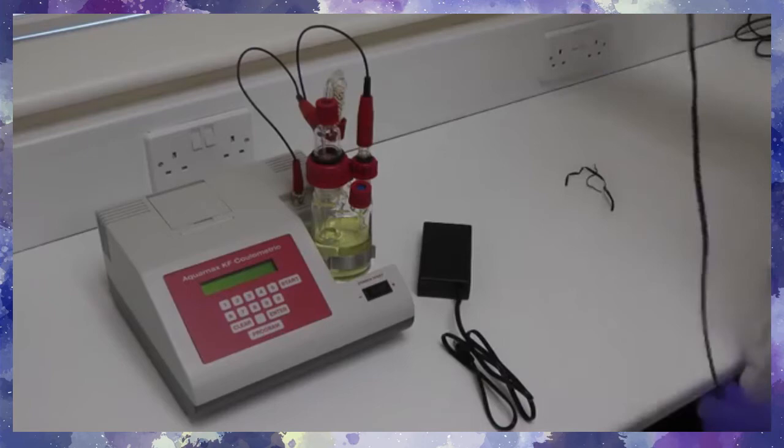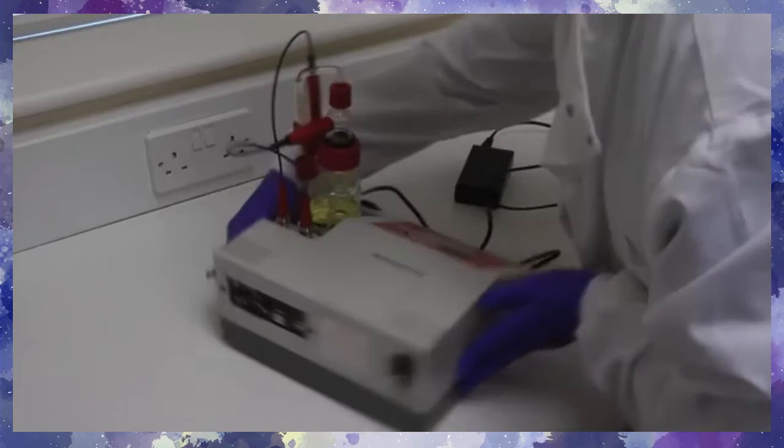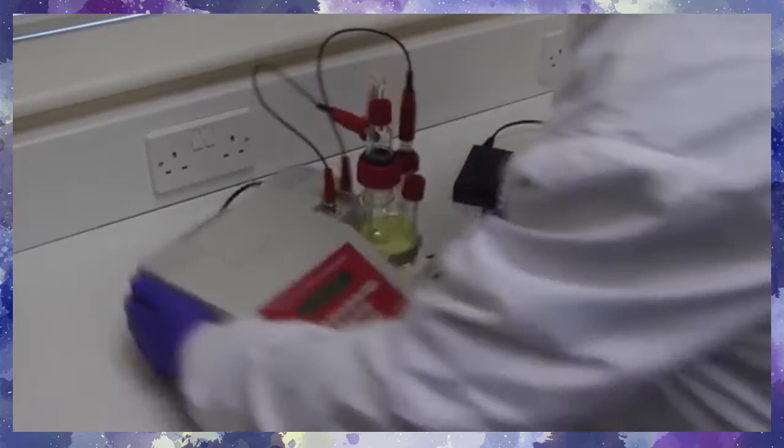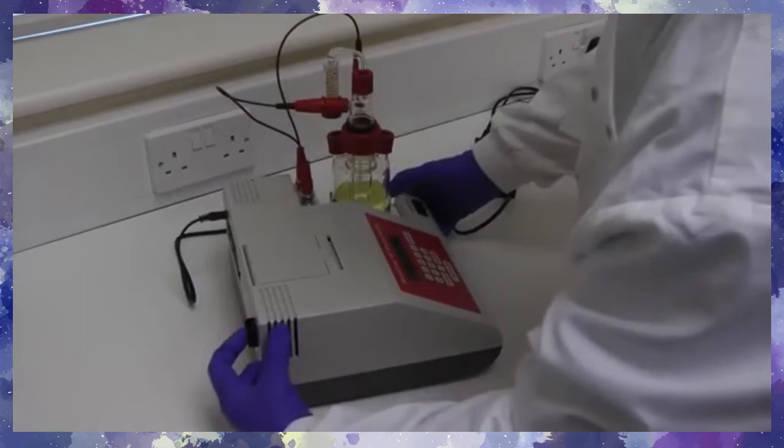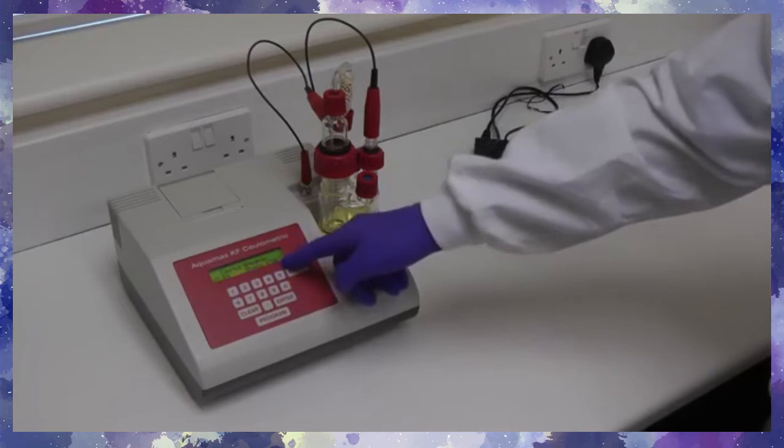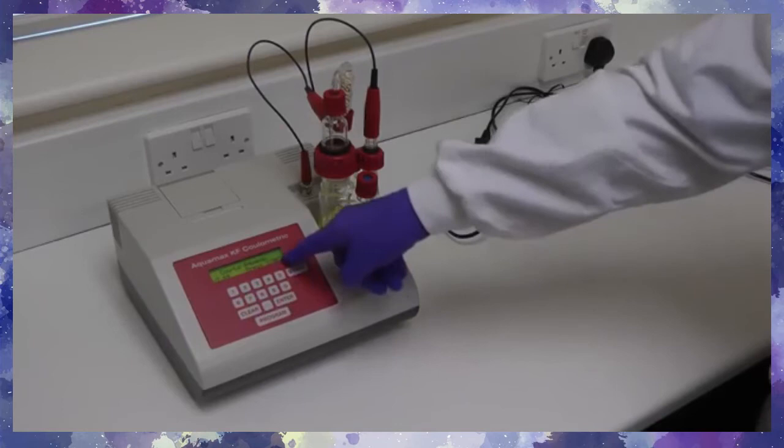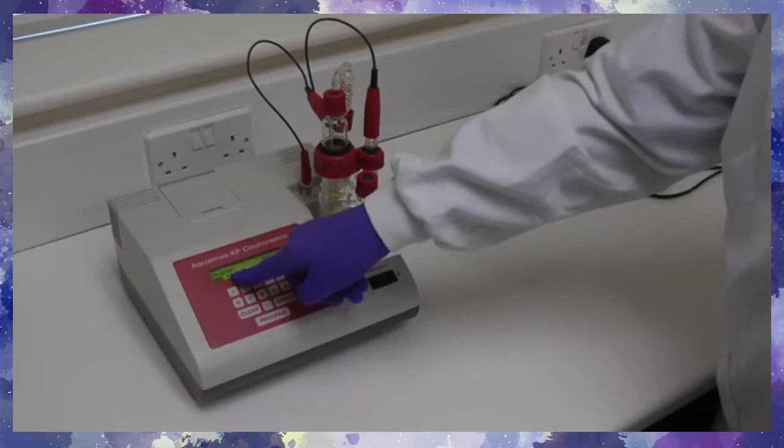To switch the instrument on, connect to the mains electricity supply using the power pack and mains cord. Press the power on switch at the rear of the unit. The instrument will then start to stir automatically, and the display will show the model, the software code, and what the operator is required to do. All other keypad functions are disabled. Press start as requested by the display. The Aquamax KF Moisture Meter begins the precondition process, showing how many micrograms of water have been titrated, the speed of the titration, and the detector signal.